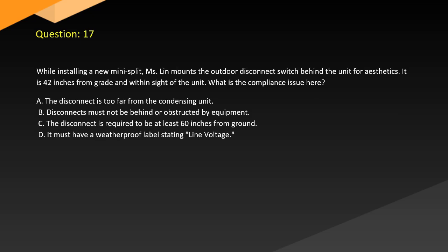Question 17. While installing a new mini-split, the installer mounts the outdoor disconnect switch behind the unit for aesthetics. It is 42 inches from grade and within sight of the unit. What is the compliance issue here? A. The disconnect is too far from the condensing unit. B. Disconnects must not be behind or obstructed by equipment. C. The disconnect is required to be at least 60 inches from ground. D. It must have a weatherproof label stating line voltage.